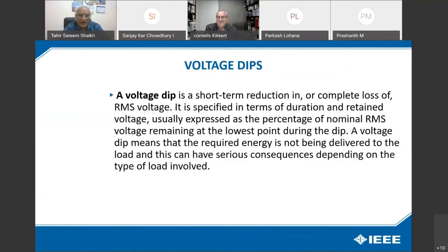A voltage dip is a short-term reduction in, or complete loss of, RMS voltage. It is specified in terms of duration and retained voltage, usually expressed as a percentage of nominal RMS voltage remaining at the lowest point during the dip. A voltage dip means the required energy is not being delivered to the load, and this can have serious consequences depending on the type of load involved.